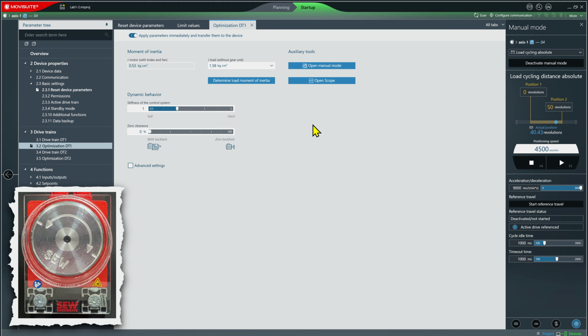Okay, pretty simple. My instructions mention one other thing I need to do, and that is to set the zero clearance slider all the way down to 0%. This accommodates backlash if a gearbox is attached. Now in our case we don't have one attached, so by setting it to 0, that says we just have a direct drive motor with no gears.